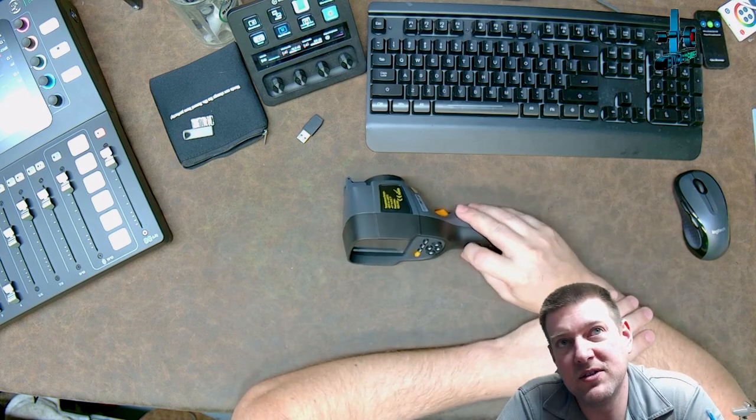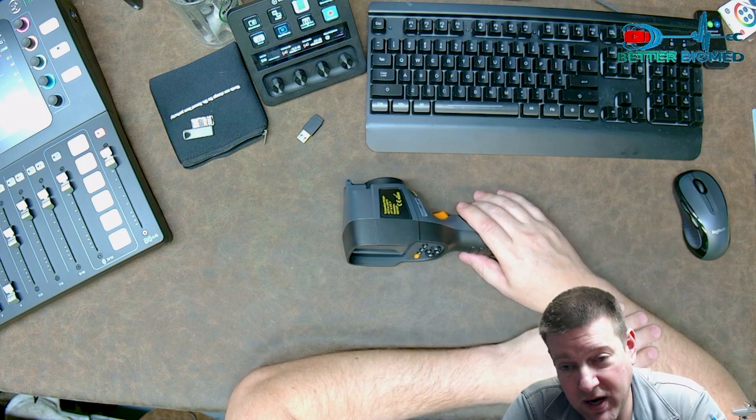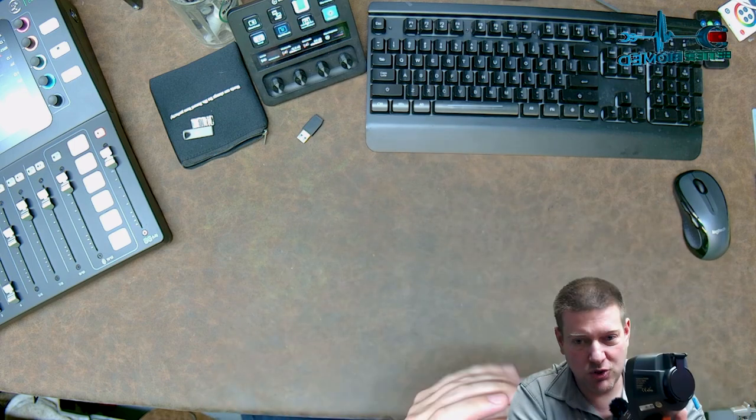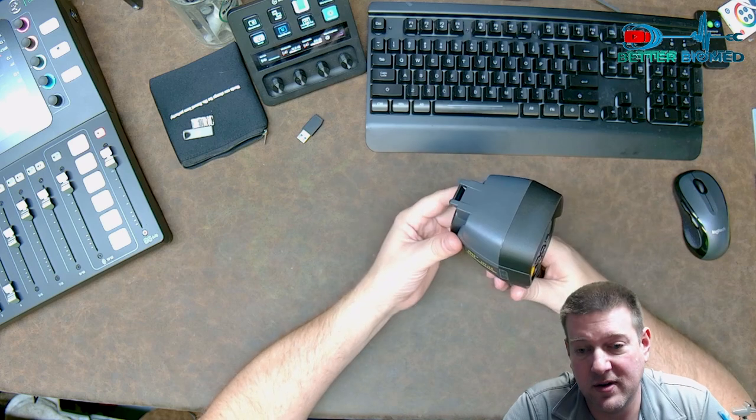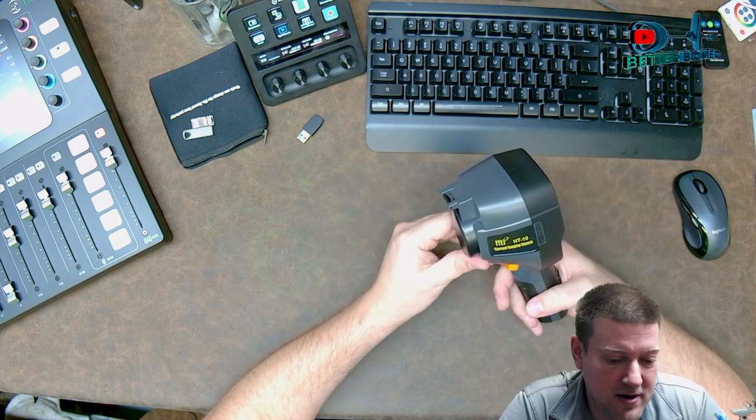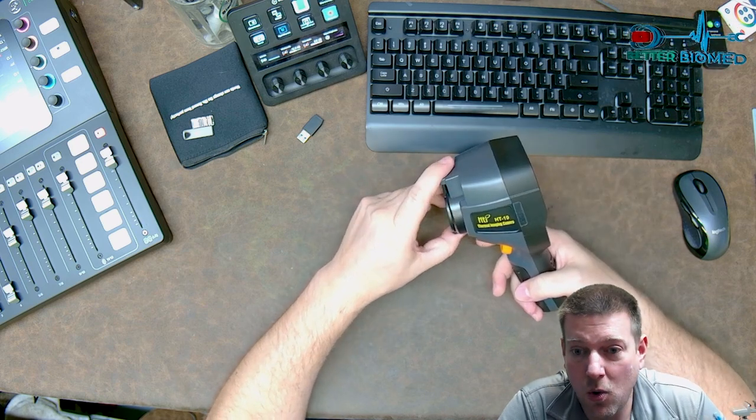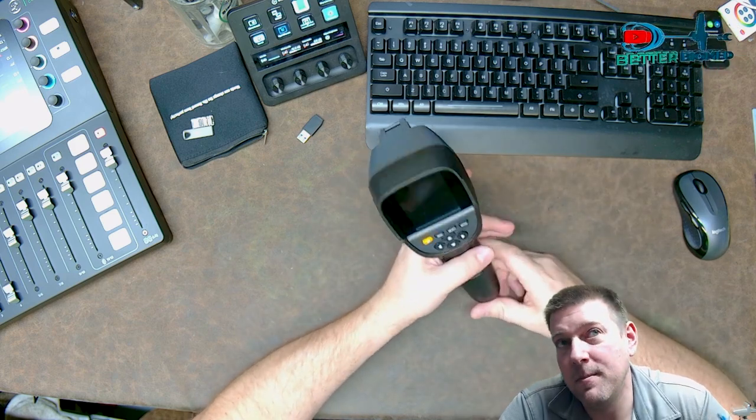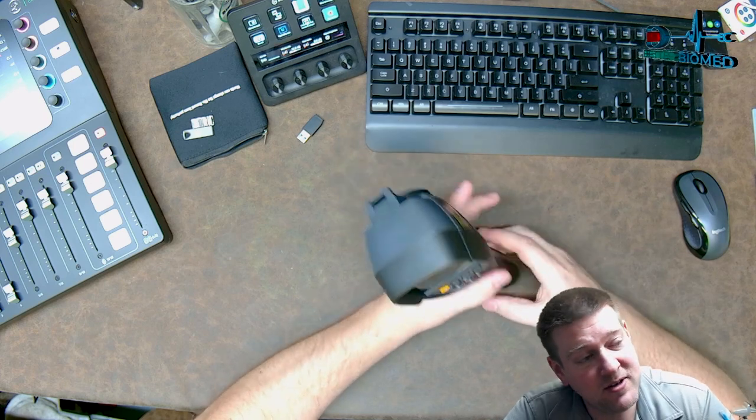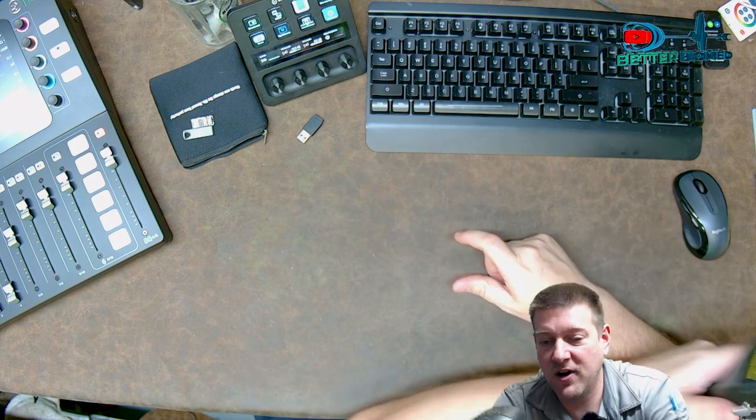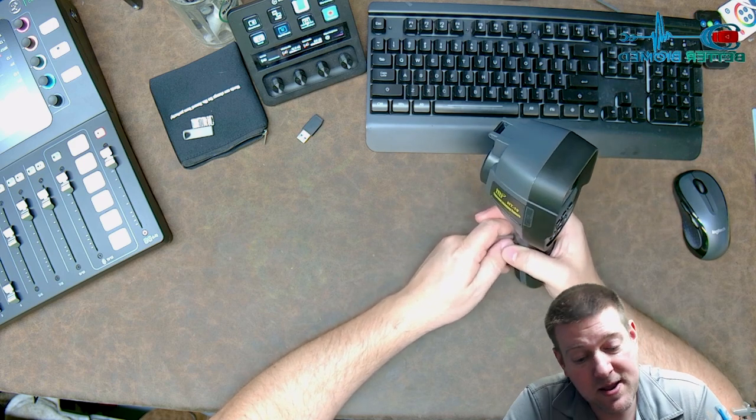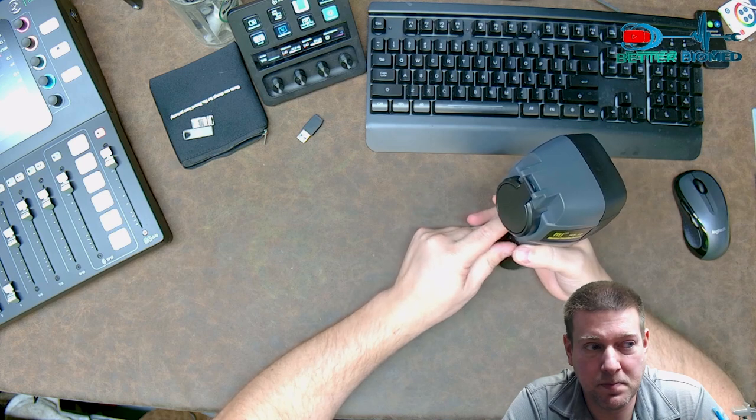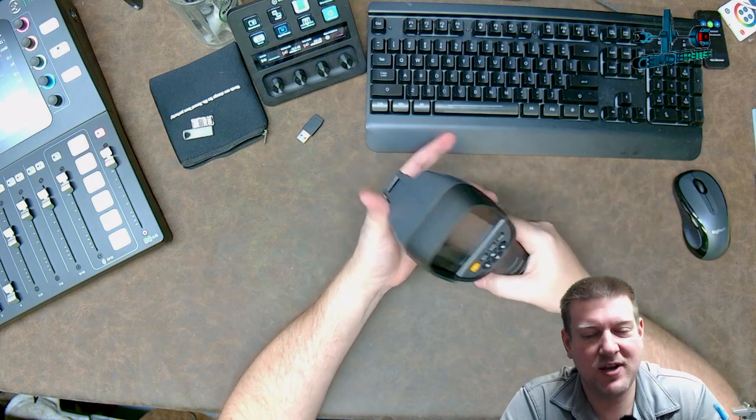Well, one of the reasons that it's used in even hospitals is, let's say you have a breaker panel. You can open up a breaker panel and you can shoot an infrared camera at all your breakers and you can see which ones are overloaded. You can tell because they're going to be glowing. They show red or they show orange or white. And you can also do that for like transformers or even ventilation rooms. Like if you go into a room that has mediocre ventilation, some of those comm closets out there in hospitals, you can use this guy right here to walk into the room and just scan all your items and you can find which items are running abnormally hot.